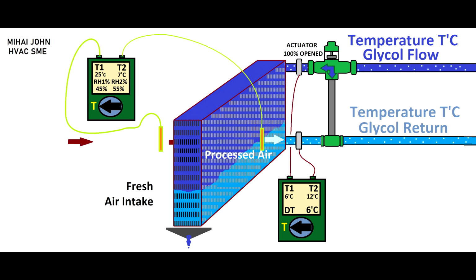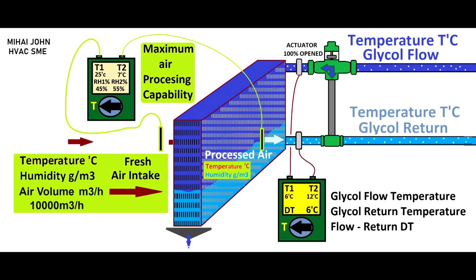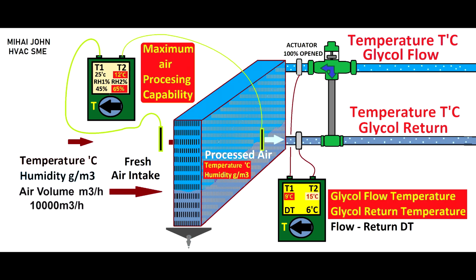Notably, we observed the glycol valve being fully open during these evaluations. Our objective is to accurately assess the cooling heat exchanger's capacity under optimal system conditions. Prior to conducting fault evaluation, it is imperative for engineers to meticulously scrutinize duly validated documents, commissioning reports, and design specifications. In the event of unavailability or absence of requisite documents, the engineer must undertake comprehensive system analysis to effectively proceed with the evaluation process.